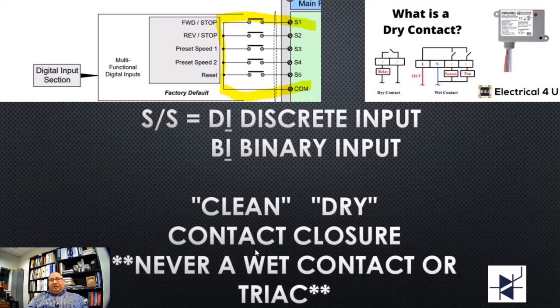SS stands for start stop. That's all that means. DI, with the emphasis on the I, means input. Discrete or binary means the same thing. We need to have a clean, dry contact closure. We could obtain that with a RIB relay, or with an isolated relay that is gold plated. It needs to be dry, meaning that it cannot be shared with any other relay. And for us to do this, we would wire S1 to common, and we would provide a dry contact here.